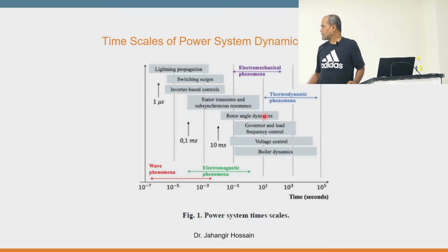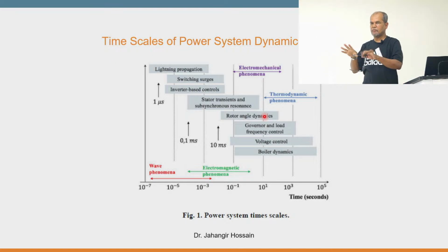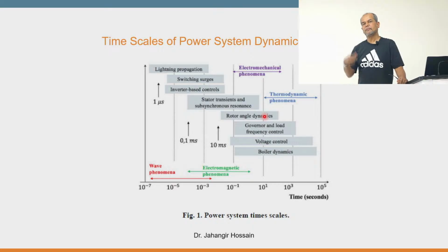So depending on your requirement and the control dynamics, you have to pick the right model and the right software. If you do your own coding, that's always fine: you write the mathematical model and then code it. But if you use existing software, MATLAB can do both RMS and electromechanical. PSS/E cannot do electromagnetic.